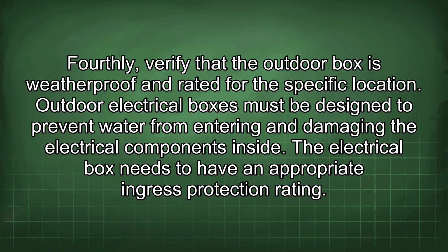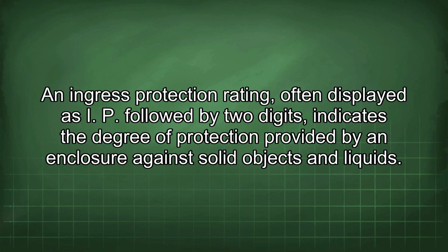Fourthly, verify that the outdoor box is weatherproof and rated for the specific location. Outdoor electrical boxes must be designed to prevent water from entering and damaging the electrical components inside. The electrical box needs to have an appropriate ingress protection rating. An ingress protection rating, often displayed as IP followed by 2 digits, indicates the degree of protection provided by an enclosure against solid objects and liquids.